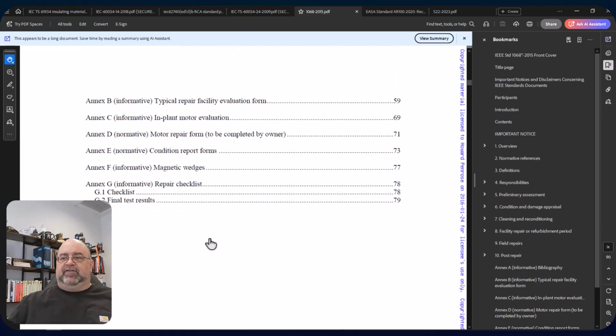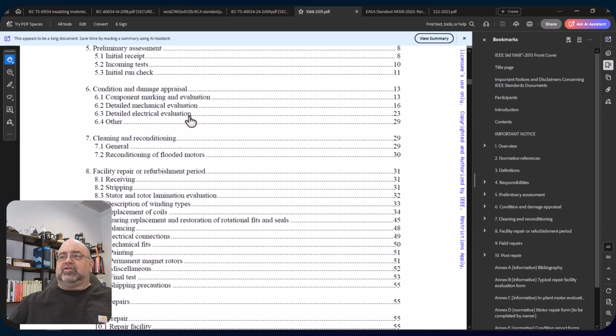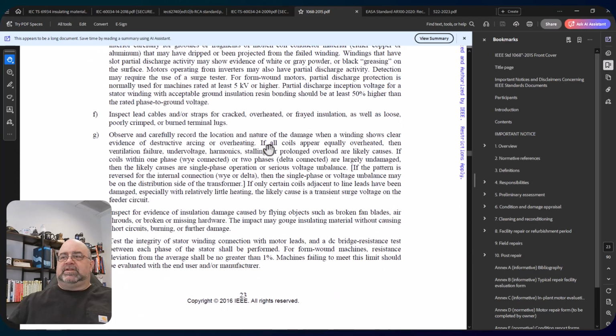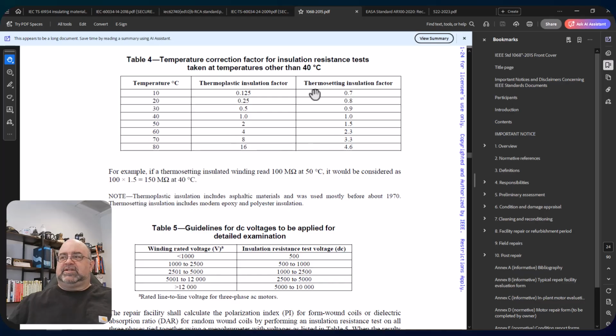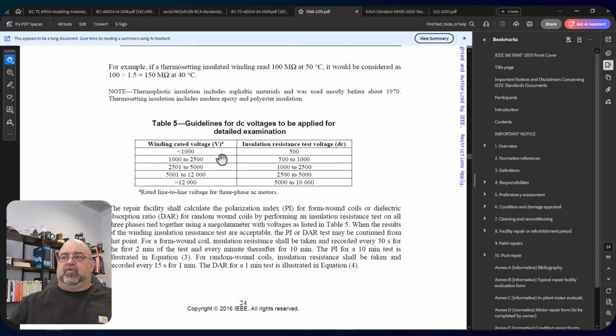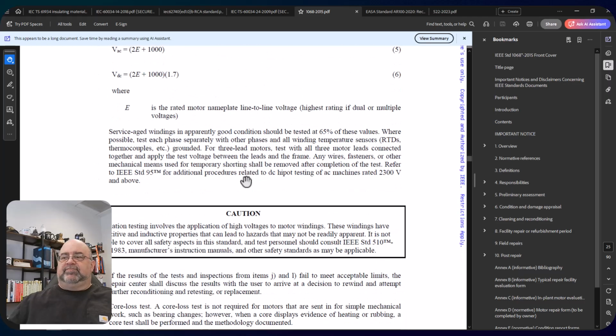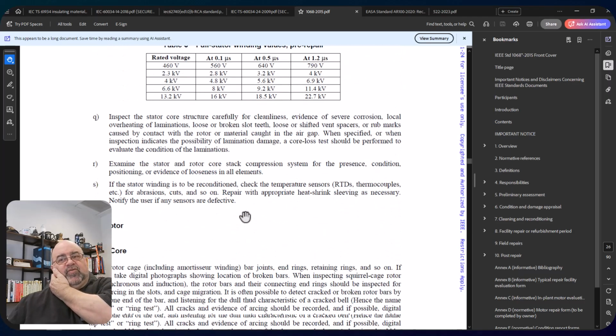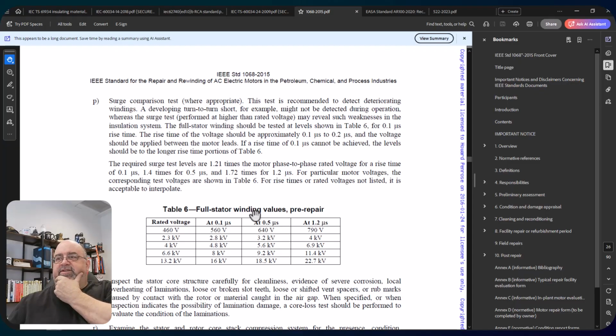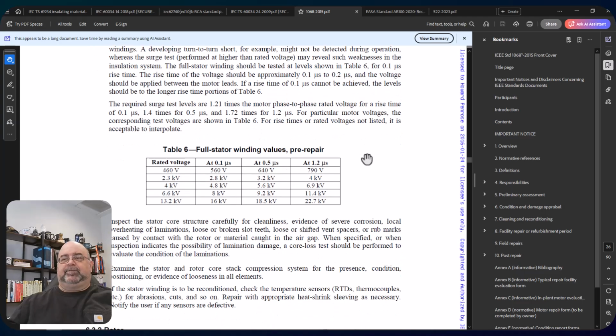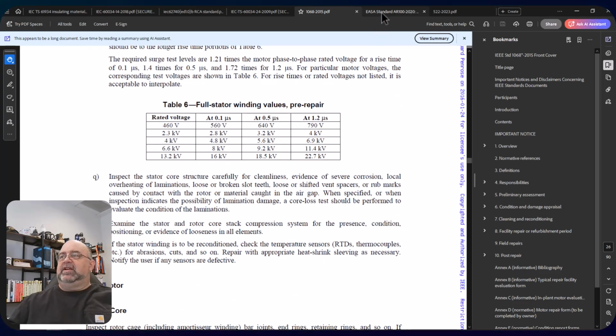Bearings and fits. Field repairs, so we want to go to electrical evaluation. So this is all the inspections, insulation resistance, DC voltages for different things. Dielectric absorption, full stator. Where's the surge test? Here it is. This test is recommended to detect. Here we go. So 460 volt would be 560, 640, or 790; 2300, 2.8, 3.2, or 4. These are much lower than twice the voltage plus 1000, of course. So it would be similar to twice the voltage plus 1000 and 75%. Okay, so wanted to get that aside. AR100 is here.